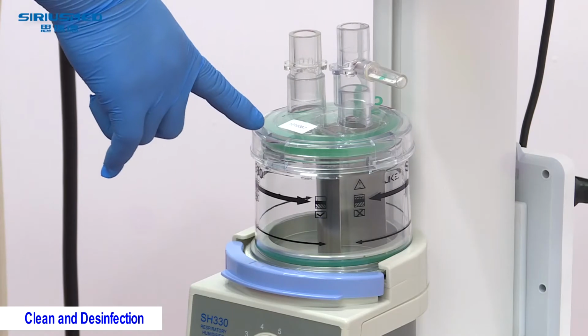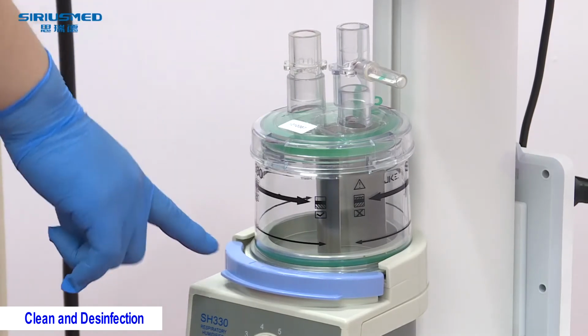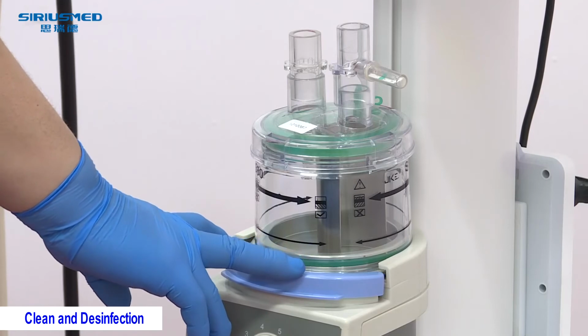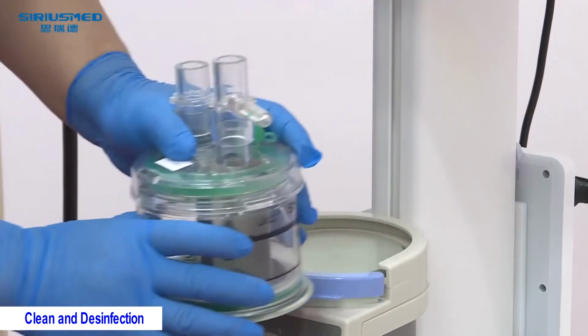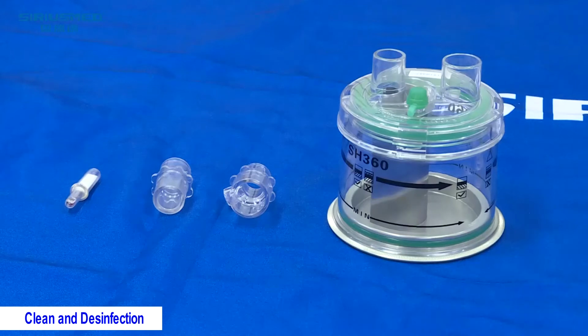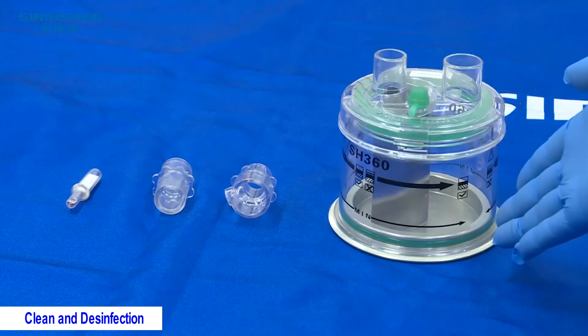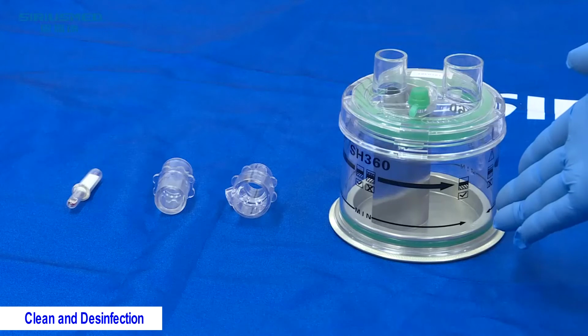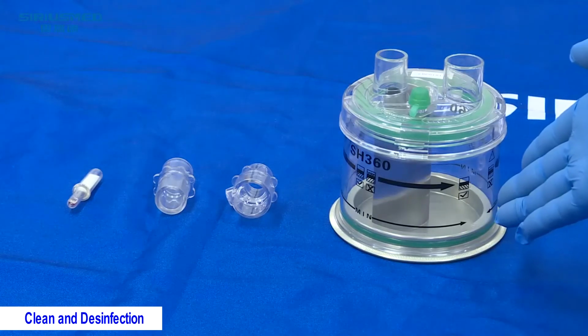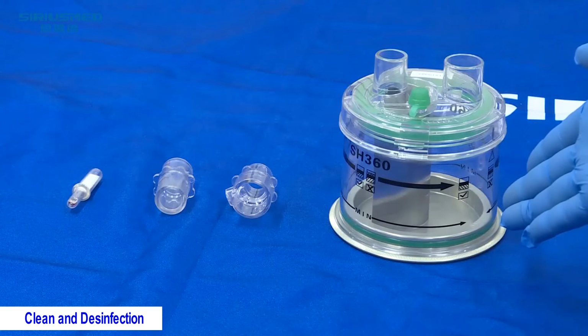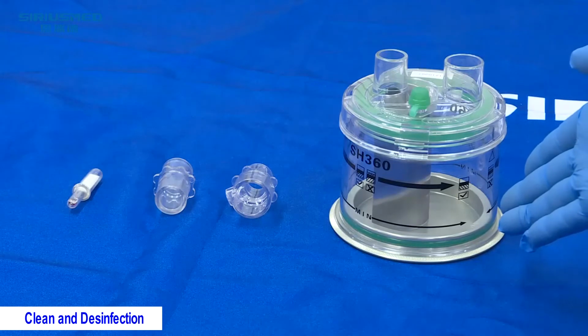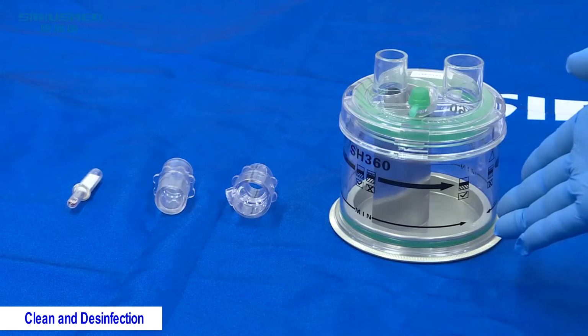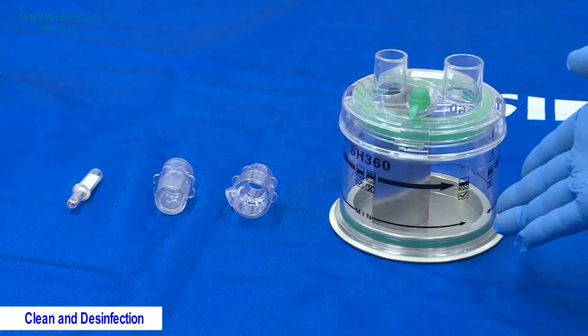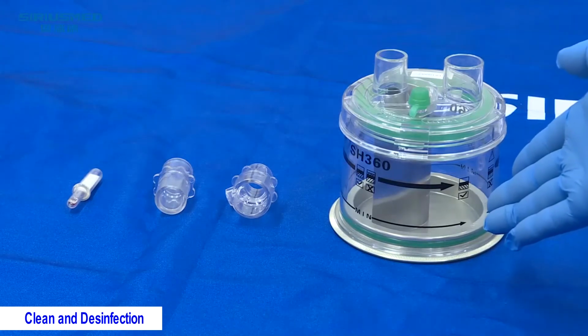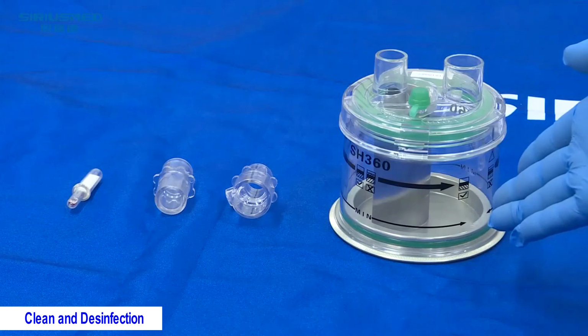And then about the humidifier part, we need to take off the water chamber. You just press this blue button and then remove it easily. This is the humidifier part, which needs cleaning and disinfection. Because we have different suppliers for this humidifier and the instructions are totally different, we suggest the end user check the user manual to find out about the cleaning and disinfection.